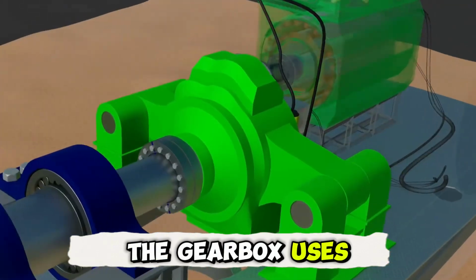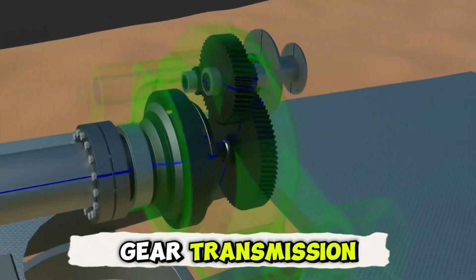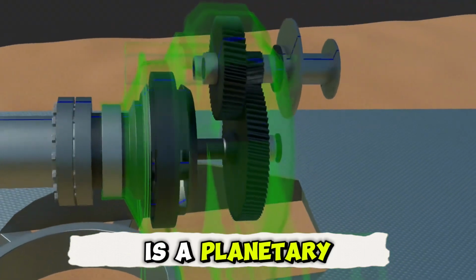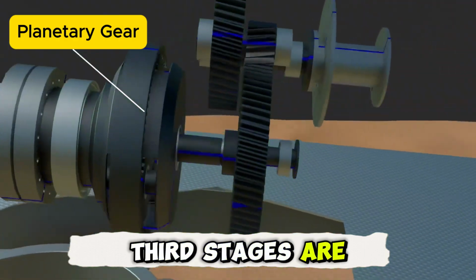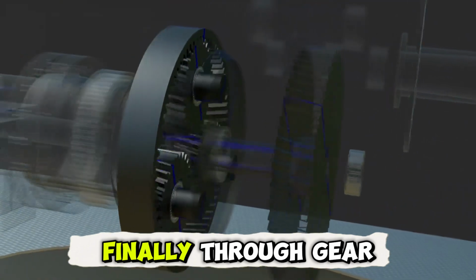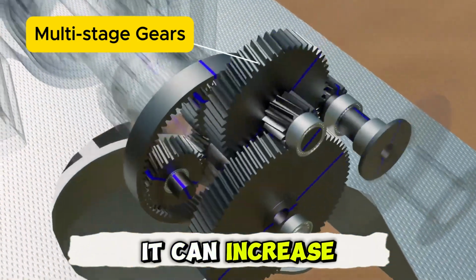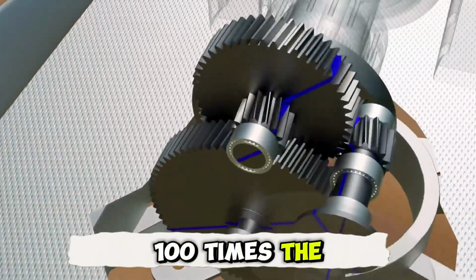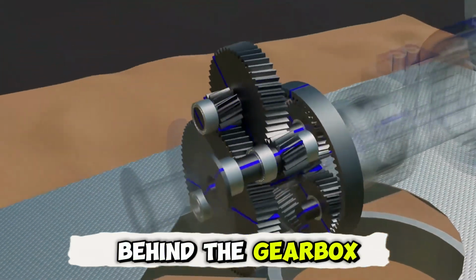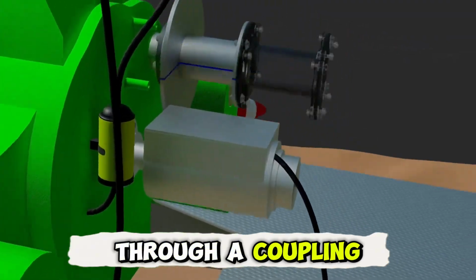The gearbox uses a 3-stage gear transmission. The first stage is a planetary gear. The second and third stages are multi-stage gears. Finally, through gear transmission, it can increase the speed to 100 times the input speed. Behind the gearbox, it is then connected through a coupling to the generator.